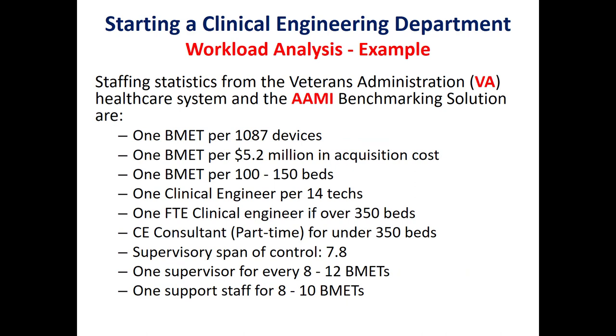After that, we should determine the size of the team inside the department. We can use a benchmarking solution such as the one made by AAMI — the Association for the Advancement of Medical Instrumentation — to determine the number of biomedical technicians, engineers, supervisors, or managers. The number of biomedical technicians can be determined based on the number of devices, the number of beds, or the number of high-risk medical devices.